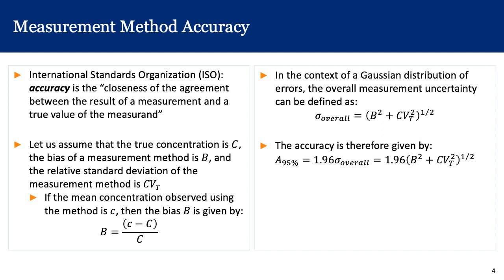Once we have defined sigma_overall, we can define an overall 95% accuracy as 1.96 times sigma_overall. The 1.96 comes from the normal distribution, where 95% of the area lies between mu minus 1.96 sigma and mu plus 1.96 sigma. So 95% accuracy equals 1.96 times the square root of B squared plus Cv_t squared.